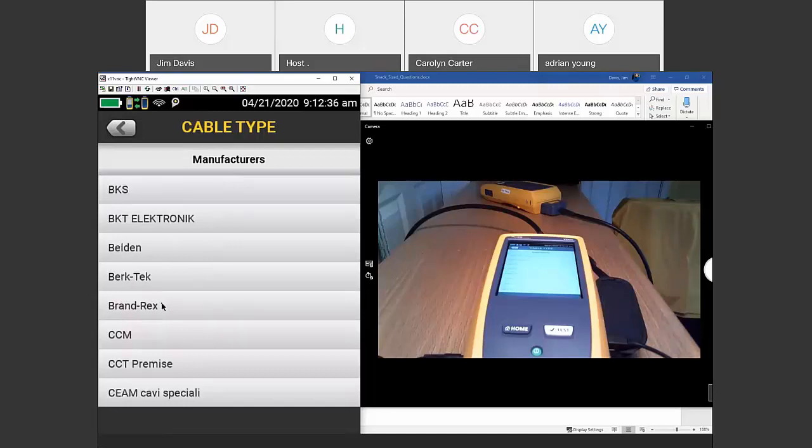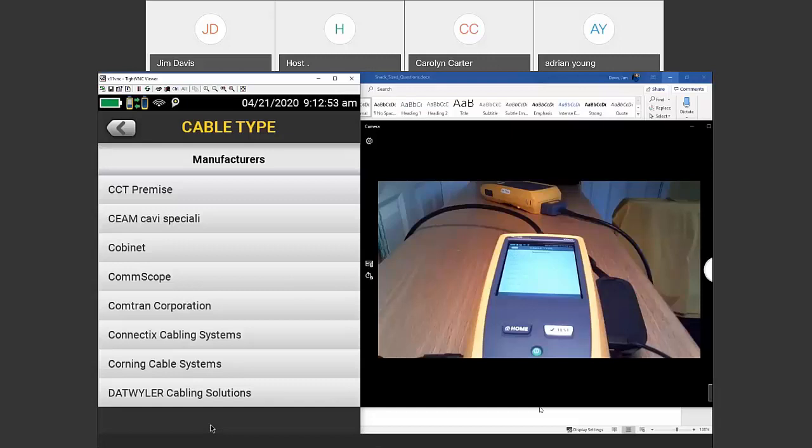And the other thing is, if you get the results in LinkWare PC, the FLW file, you can actually recertify the results with the NVP value that you would like, to see what that cable difference is. And you'll probably see it's actually very small, so it's nothing to be really concerned about. But if you are concerned about it, definitely talk to your contractor and say, hey, please enter the correct NVP, but it's not the end of the world.